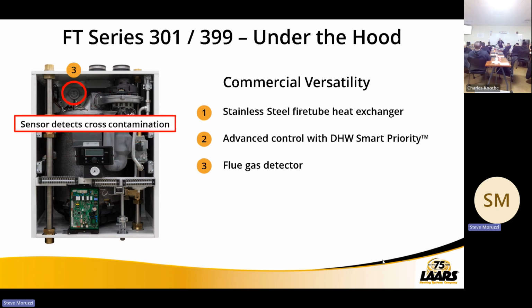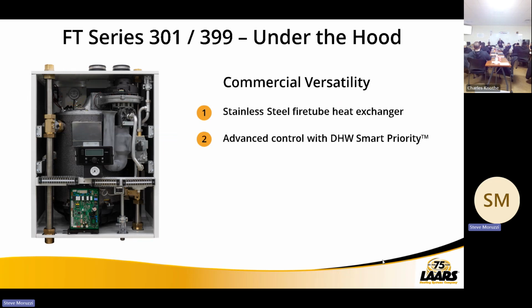So now we have a built-in flue gas detector. And what I want to talk about here is this is a negative cabinet. What do I mean by a negative cabinet? Combustion air is brought to the cabinet. So right here, we have a collar with the screen for that, to protect that combustion air. And that comes right into the cabinet. On the other products we had talked about, we have a rubber boot, ducted to the blower, right? So you've got your boot inside there, combustion air is brought to here, and then that comes right into the blower, right? This is combustion air that comes to the cabinet.